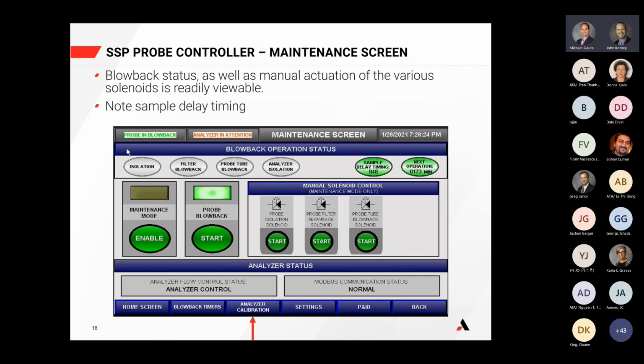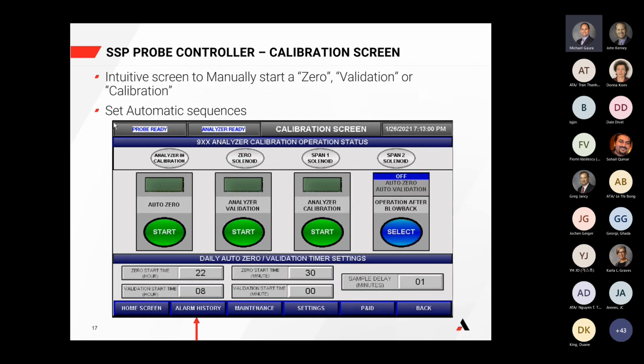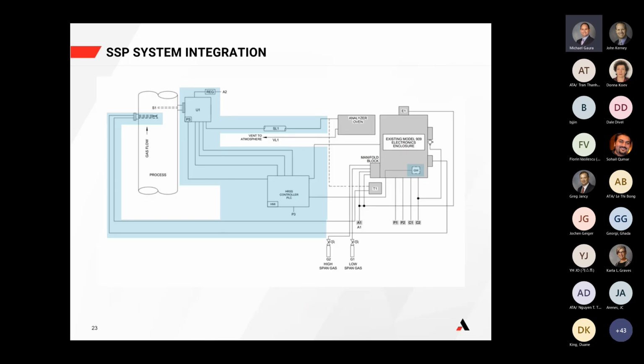I just saw a question come in about the PLC box not being maintained at 190C. Again, Rod, I don't know if you can go to that final schematic. The controller is sitting separate from the actual probe box. When Rod mentioned the enclosure temperature, it's referring to the blowback assembly. So that's the enclosure, the heater, and the probe, all right there. That's what we're maintaining at temperature, not the PLC controller box. We're not keeping that at 190C. Yeah, it's just this whole upper area that is wetted and needs to be maintained at temperature.